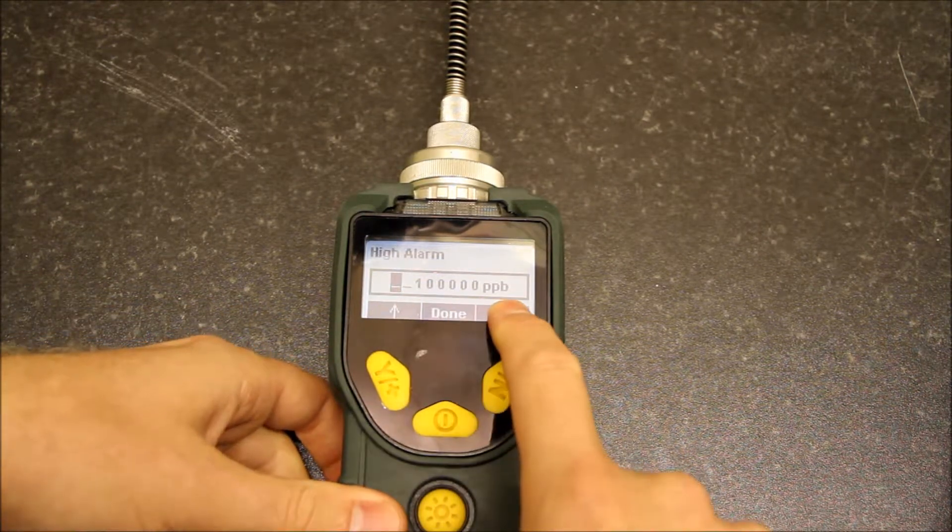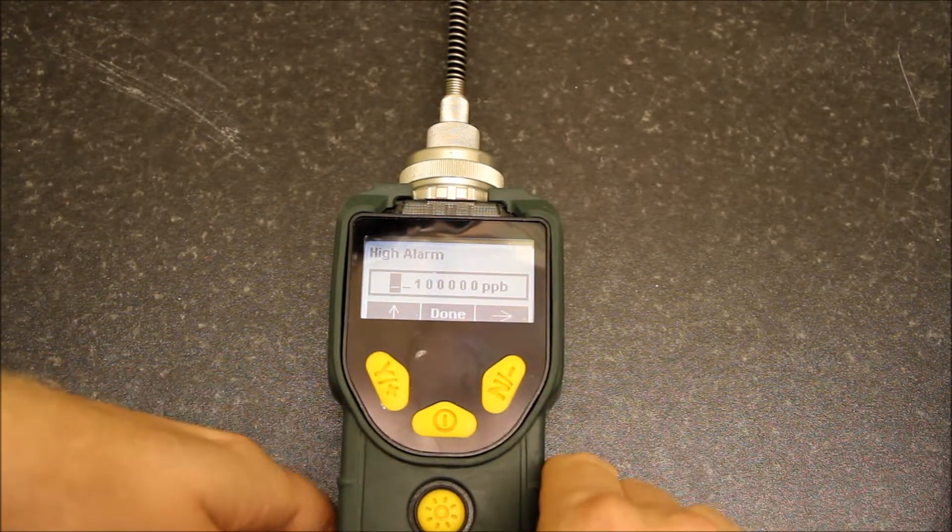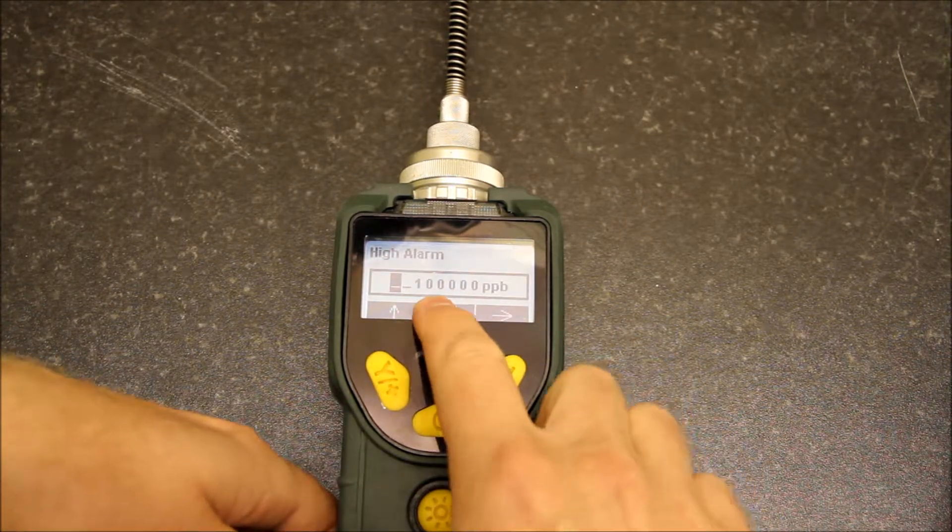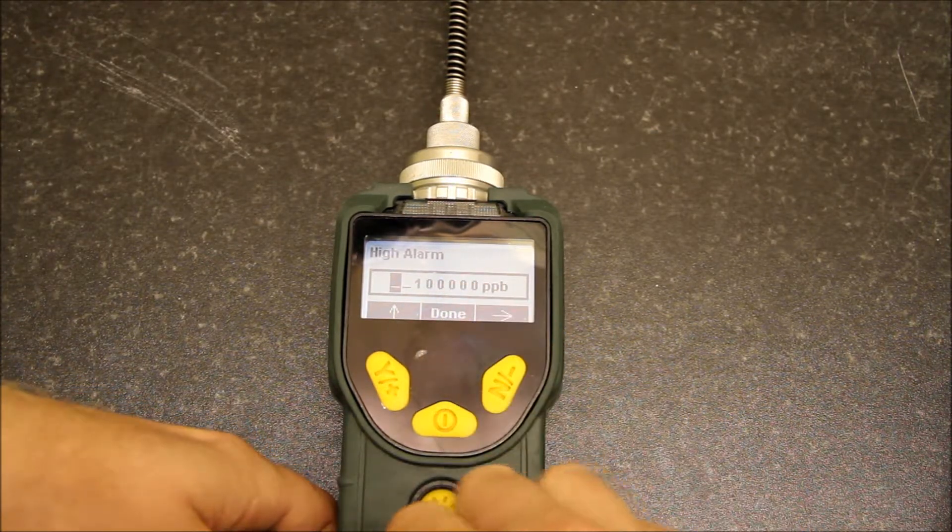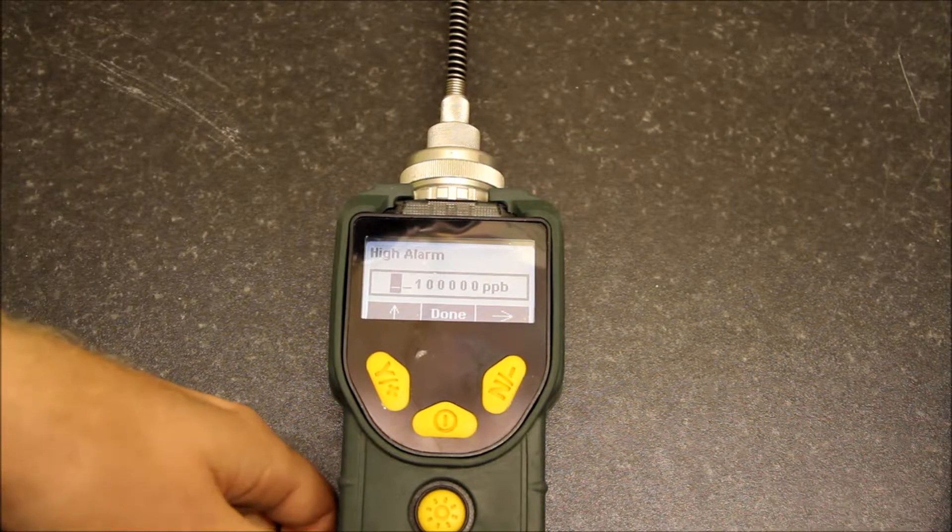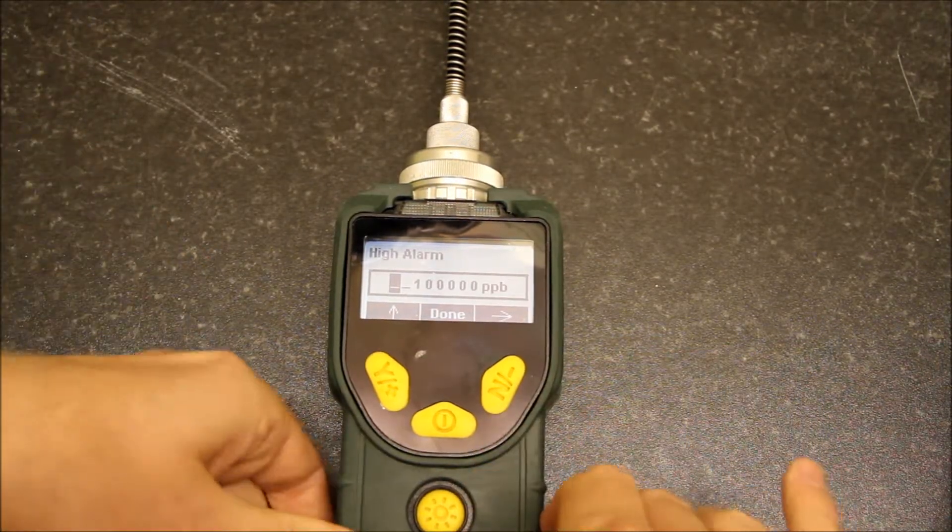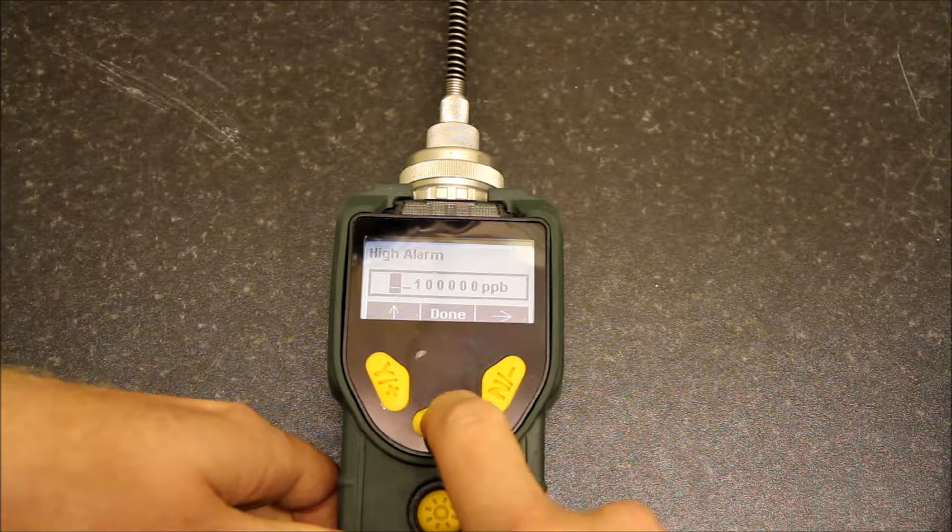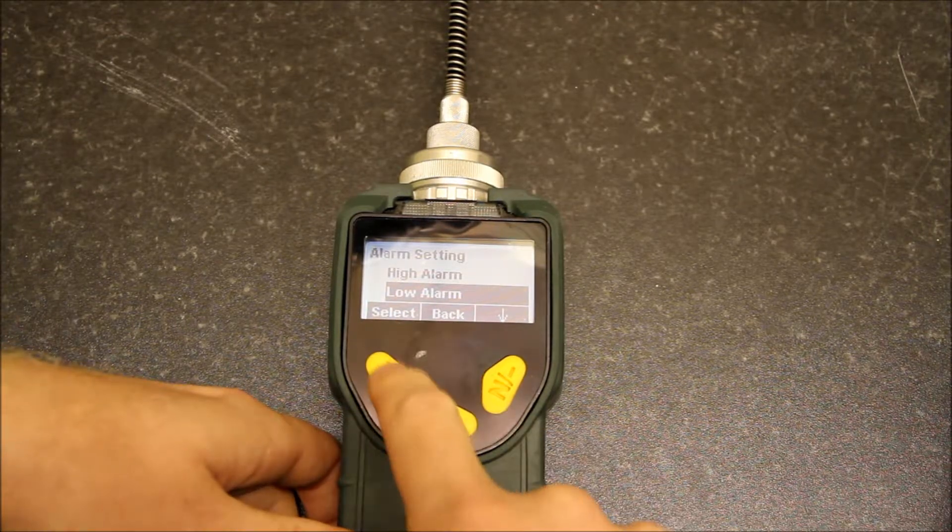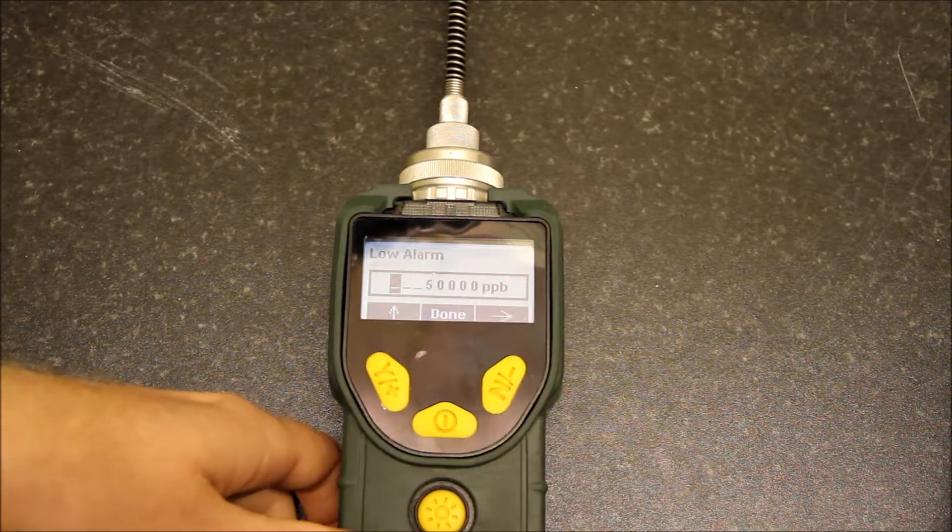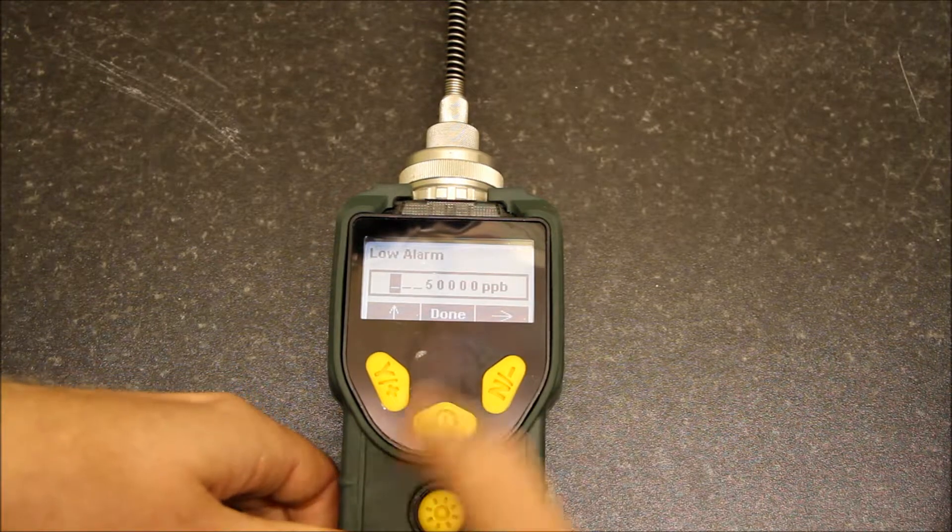You can change this to whatever you want. If you change it to all zeros, you won't have an alarm. Low alarm is the same, set at 50 ppm. Change it to all zeros and you won't have an alarm.